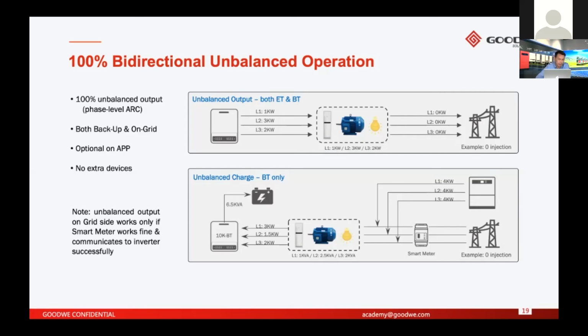It means on the grid side, the unbalanced function is an option. You can activate this function on the application when doing commissioning. But on the backup side, you don't have to do the commissioning. It's a default function. It always realizes unbalanced output, because the backup side is not connected to the grid. All right. So it means you can connect different load power on the backup side. You don't have to worry if it can support all the loads. Okay, they can do that, because the inverter can do unbalanced outputs.